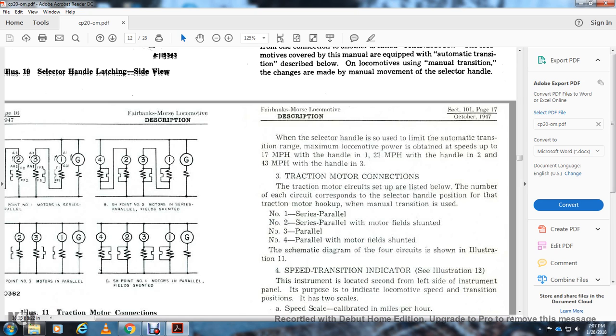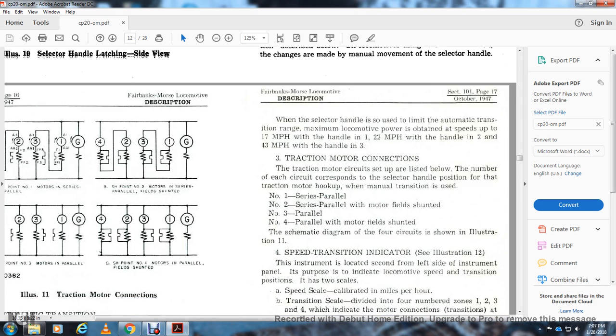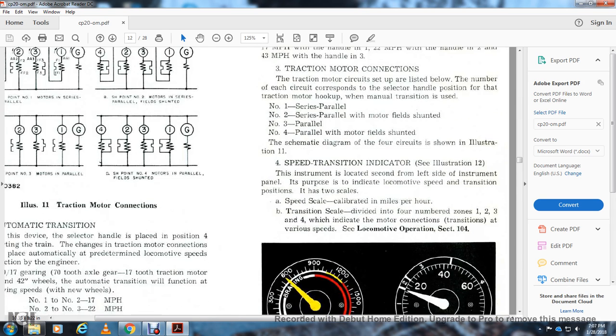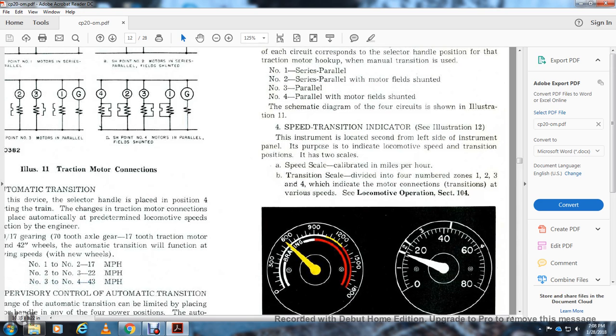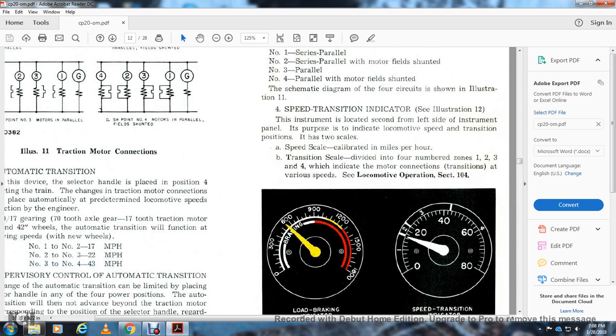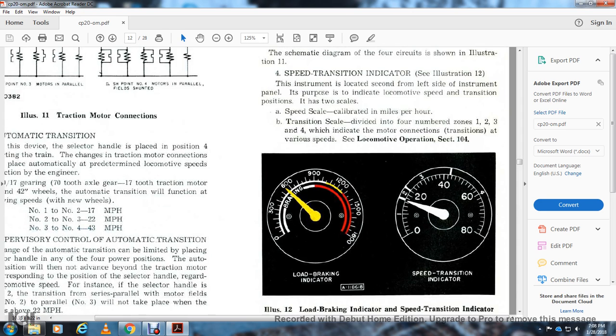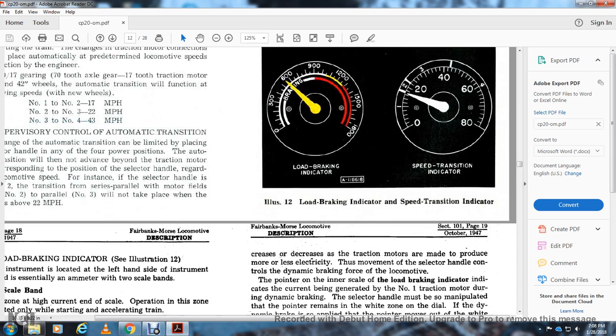The speed transition indicator, see illustration 12, is located on the left side of the instrument panel. It indicates the locomotive speed and the transition position on two scales. The first is the speed scale, calibrated in miles per hour. The transition scale is divided into zones 1, 2, 3, and 4, indicating the motor connection at the various speeds. See locomotive operation, section 104. Illustration 12: load braking indicator on the left, and speed and transition indicator on the right. Alright.